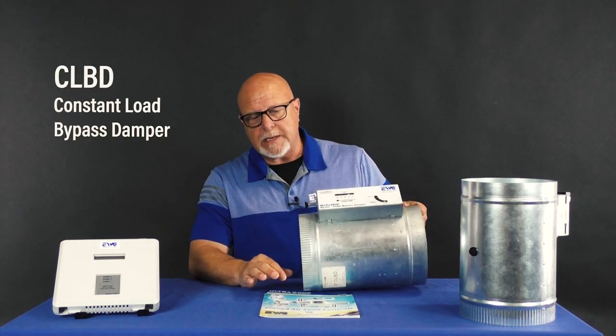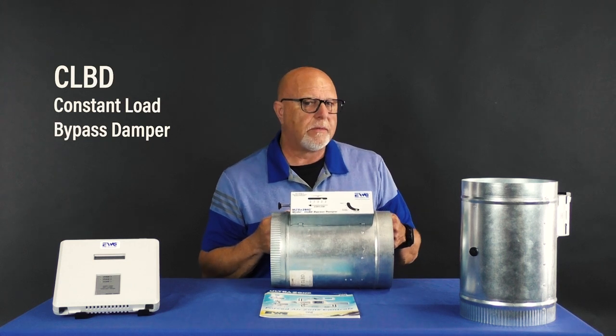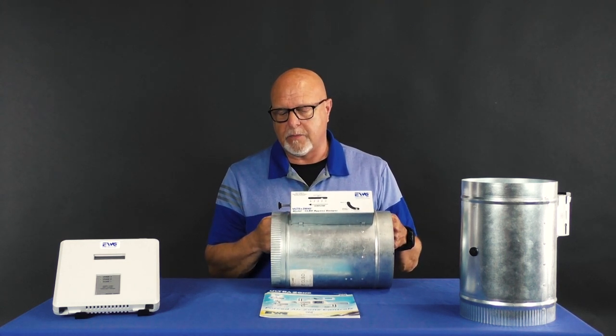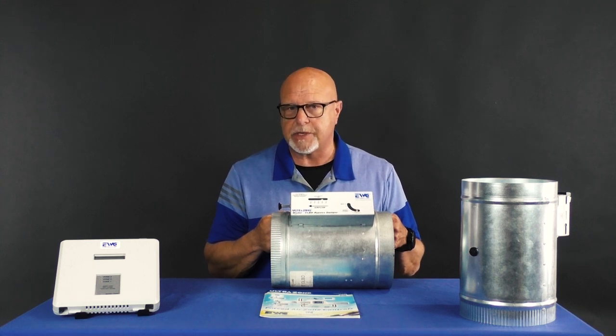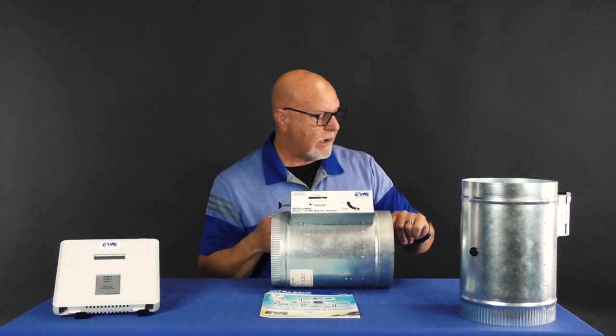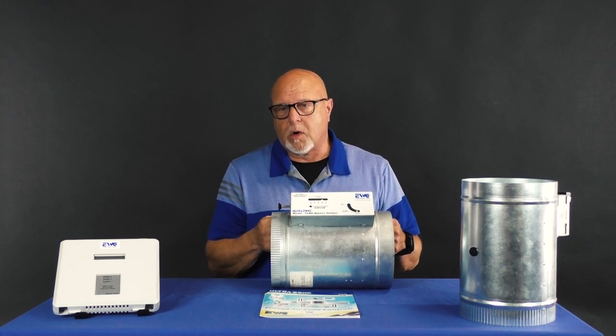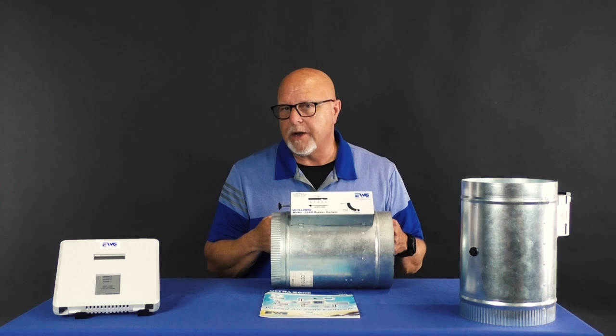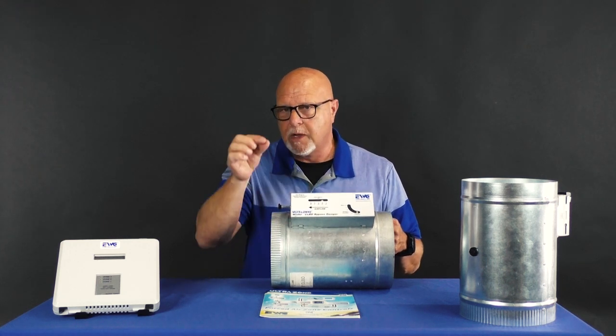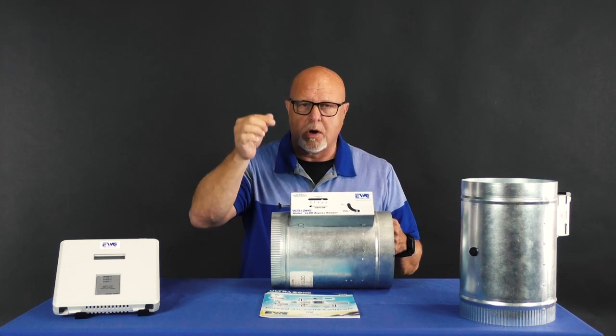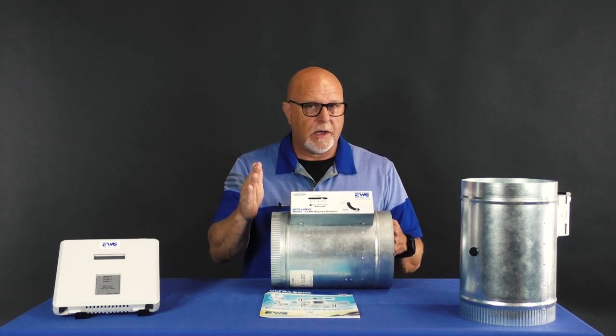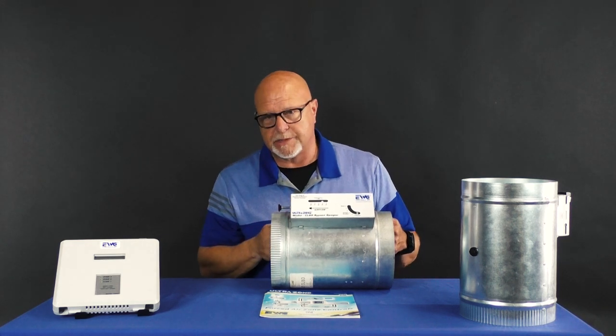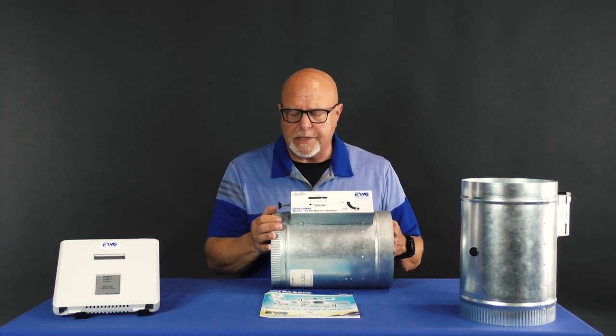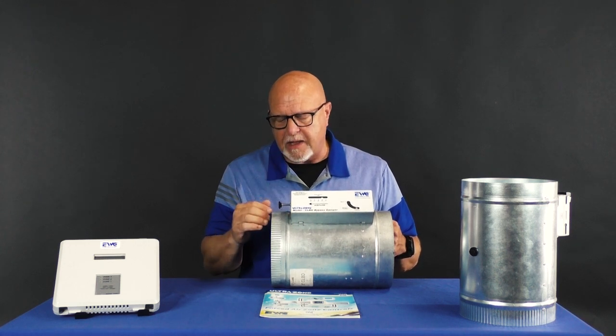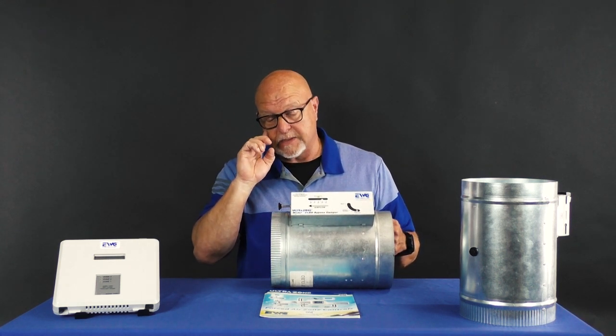First and foremost, and probably the most economical, would be our CLBD, which we did away with the old weighted arm barometric bypass that we all grew to have a love-hate relationship with over the years. Many people could not figure out how to set it up or how to install it. It was very cumbersome. It was very hard to set up because it mostly became a guessing game with moving the weights up and down a metal arm or a shaft. And do I put the shaft in the 7 o'clock position, or do I put it in a 5 o'clock position? So what we did is we developed what we think is a better way and a more accurate way to handle that excess capacity.